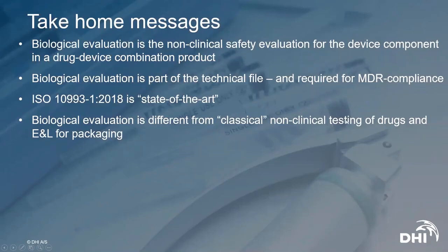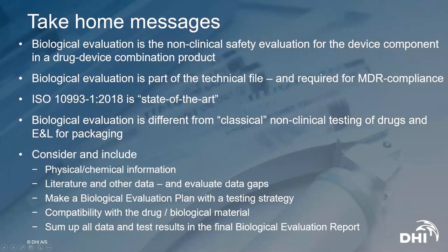For instance, implantation testing for a device component cannot necessarily be addressed by the classical non-clinical testing and toxicology performed for the drug itself. And then you have to include in your evaluation physical chemical information for the materials in the device, that you conduct a literature study and consider other data on the materials and on the device, evaluate data gaps.